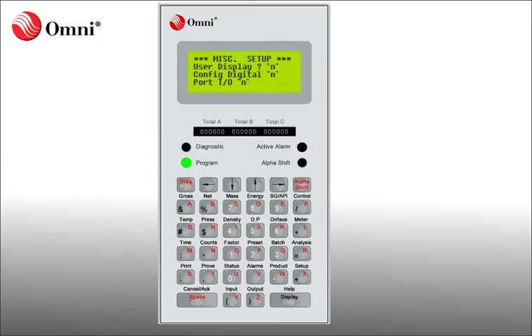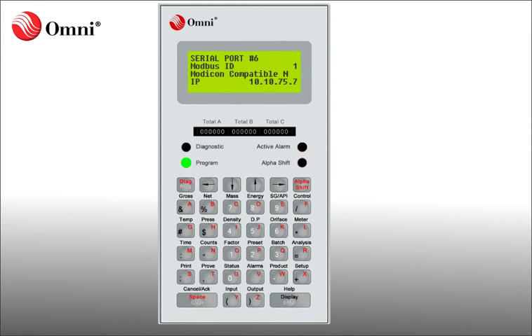It's important to note that any time you see the N on the Omni 6000 menu it requires an actual number. In this case we must know which port number has the Ethernet port. In this example the Ethernet port is port number 6, so I will enter the number 6 at the port IO N and press enter. The information on serial port number 6 shows on the screen including the IP address.